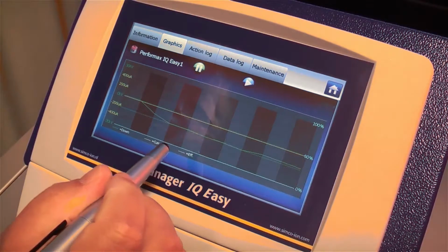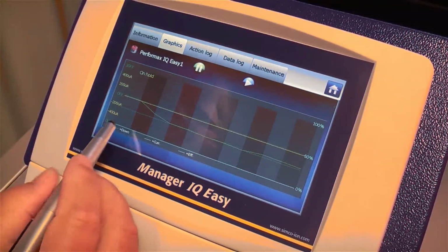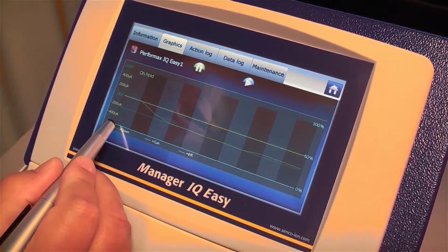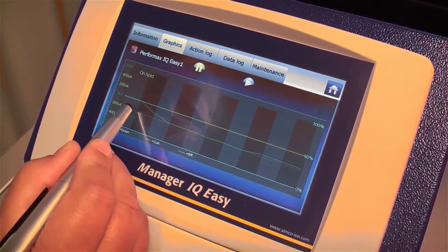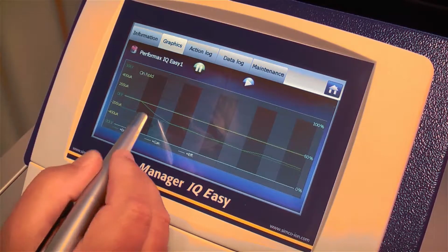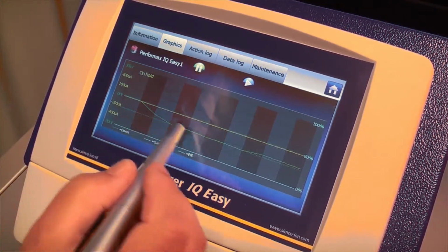You can press the graph and it will hold. We can see now here the scale of the graph is minus 30 kilovolts, meaning half of the scale is 15 kilovolts. So this is close to 11, 12 kilovolts. It is exactly the same as I have set in the charging generator.